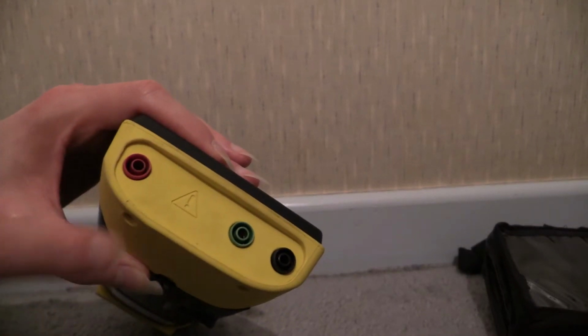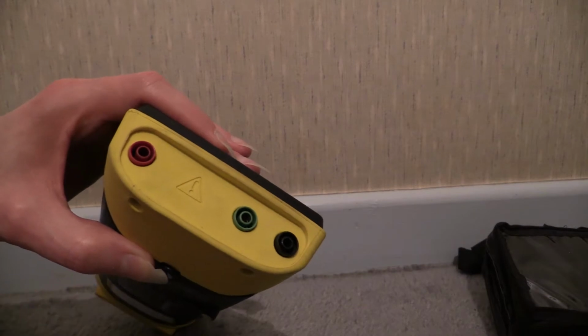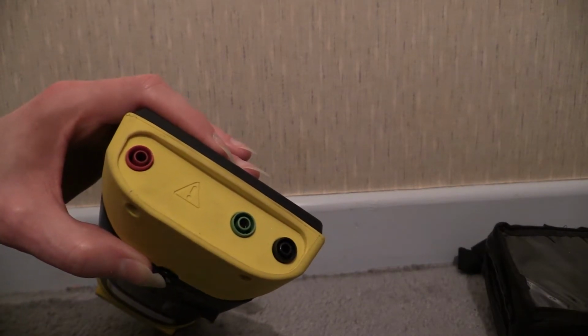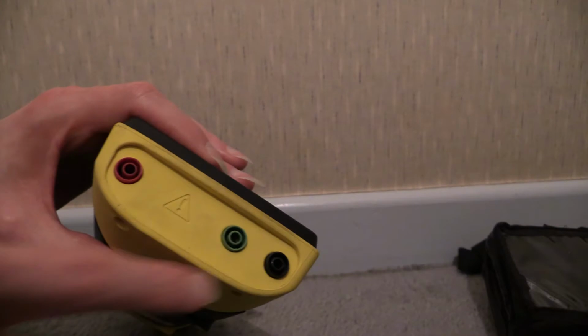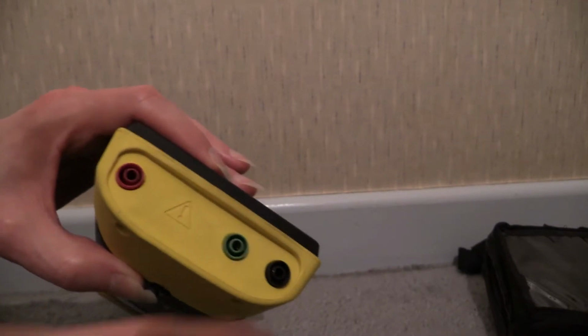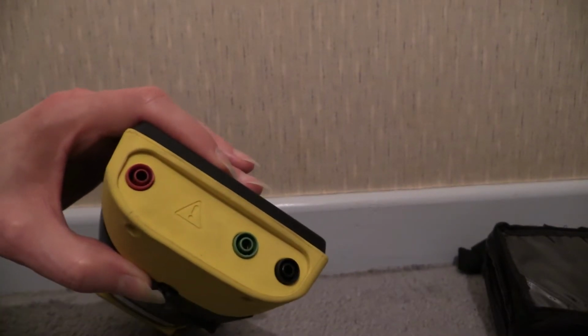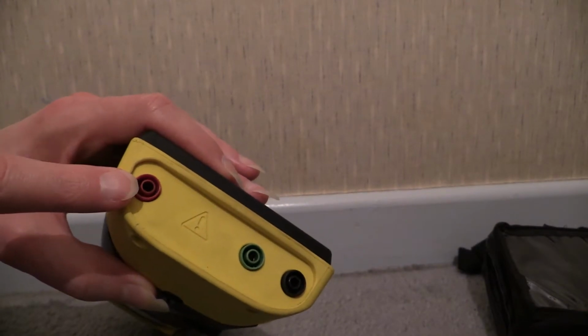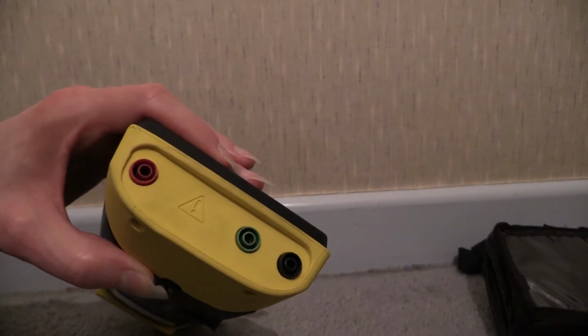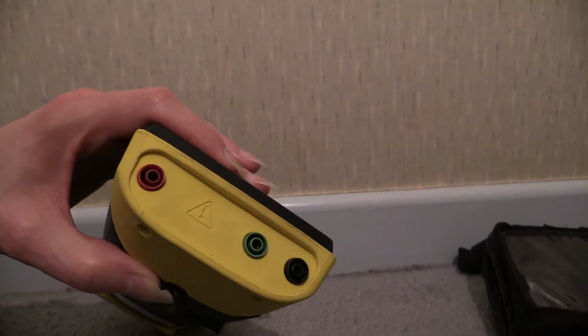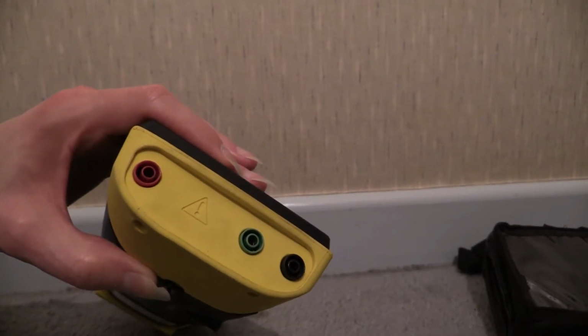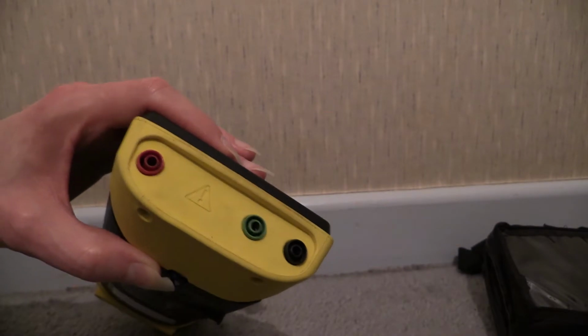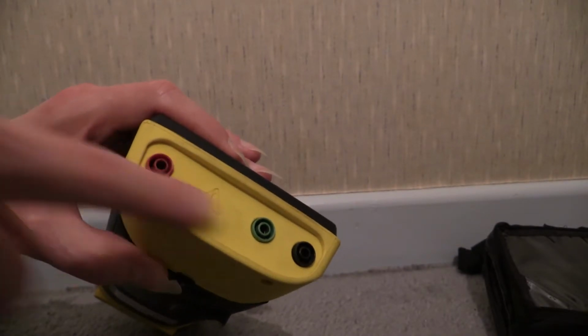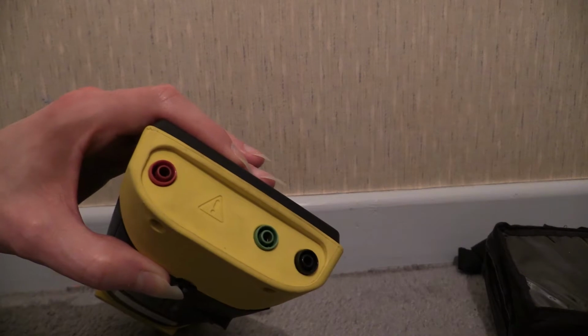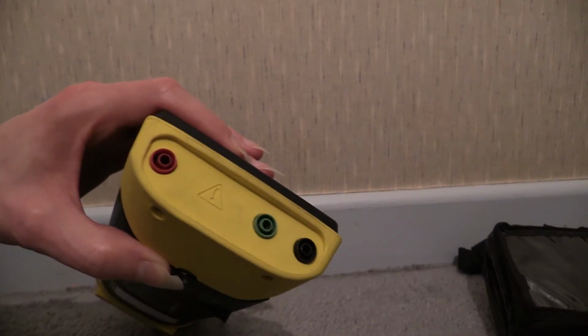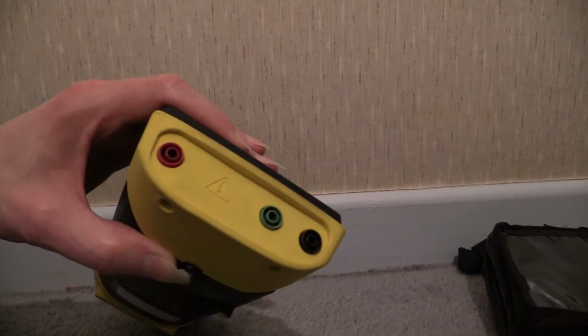When you get this, you get 3 sets of test leads. One will be green right the way down the length, and you put it in there. One will be black right the way down the length, and you put it in there. And another one will be red, and you put it in there. Now there is this third test lead, which you use for things like RCD testing and PSCC—it has 3 plugs on one end that go into all of those, runs down the cable, and on the other end you'll have a 13 amp plug.